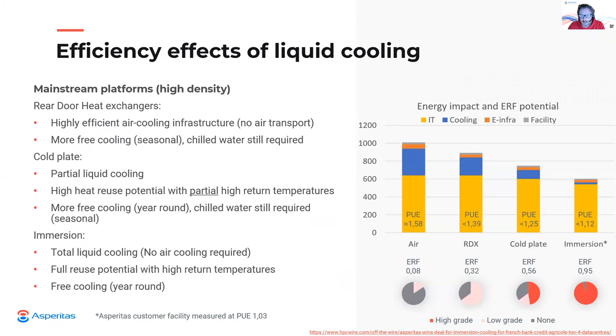This becomes clear when looking at the more explicit effects of liquid cooling strategies. Rear door heat exchangers are very efficient due to the usage of water as the main coolant circulating throughout the facility. This enables more efficient distribution and transport of heat and more efficient cooling. It is, after all, easier to exchange heat with water than it is with air. However, because they function in the same way as air handlers, low temperature cooling will still be required.